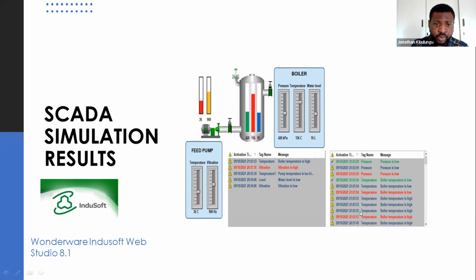Same with the feed pump: when the pressure, temperature, and vibration go beyond the predefined value, there will be alarms and different messages sent to the screen.